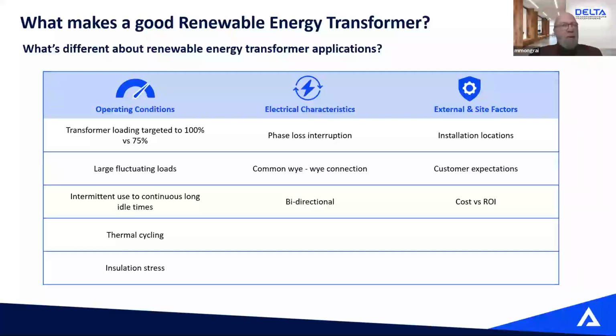So I would say my base of comparison is always a standard distribution transformer installed in an electrical room feeding a panel with multiple types of loads. So let's take that as a base of comparison. Renewable energy transformers are different beasts, supplying different types of loads in a different type of environment. A standard distribution transformer usually has a pretty steady load, fluctuating from maybe 50 to 75%, depending on the time of day and the building.